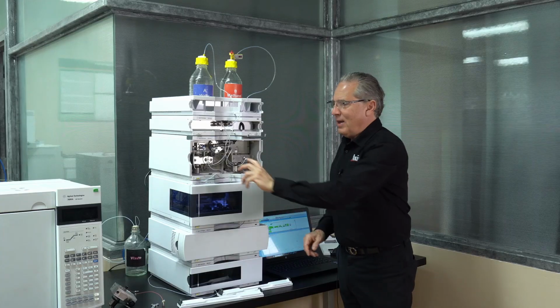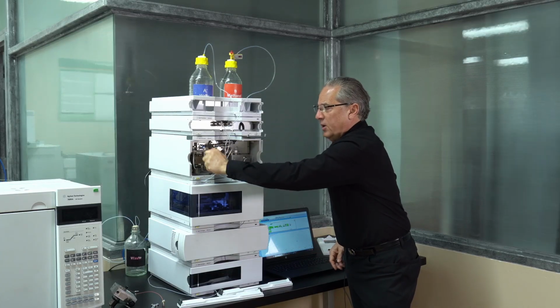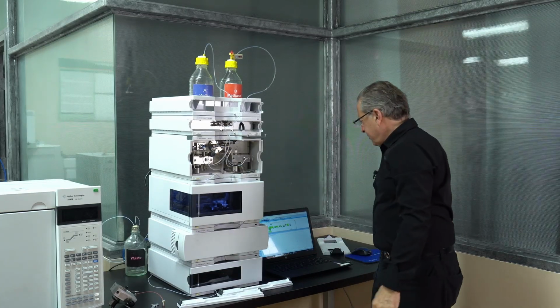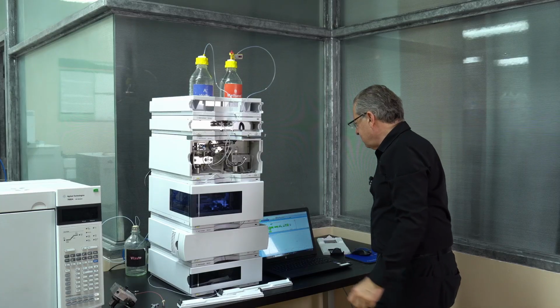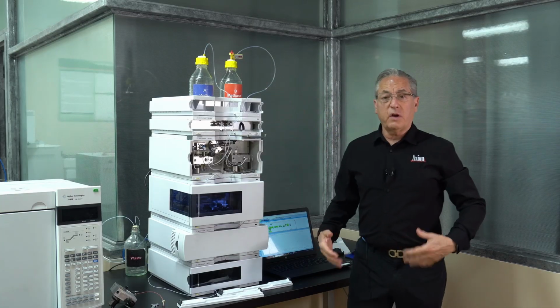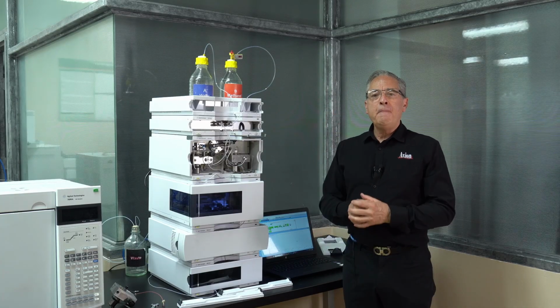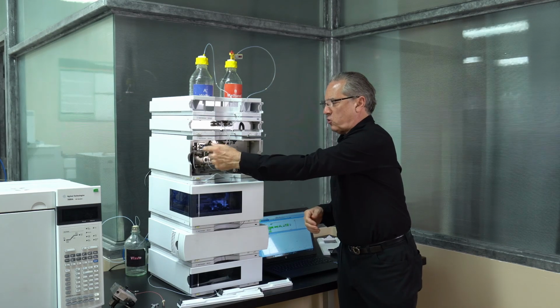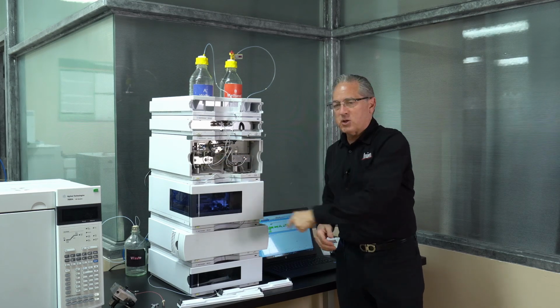When I open this up, it's going to drop to 0. So I open it up. You see the pressure drops to 10, drops to 5 bar, 9 bar. So it drops to a very low bar. And that means I'm pumping straight out to waste. I'm not pumping through the instrument anymore.